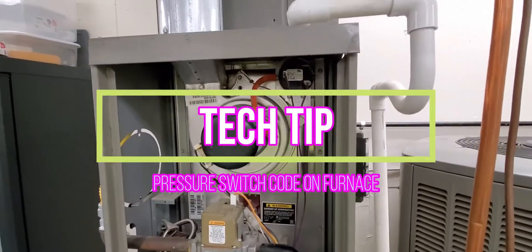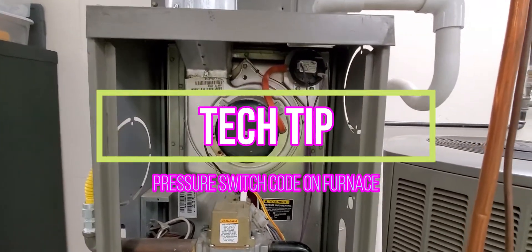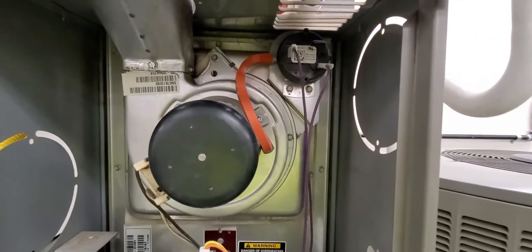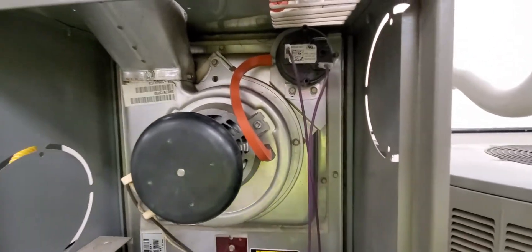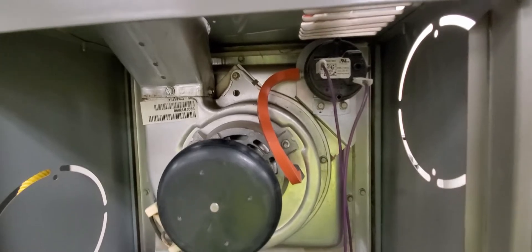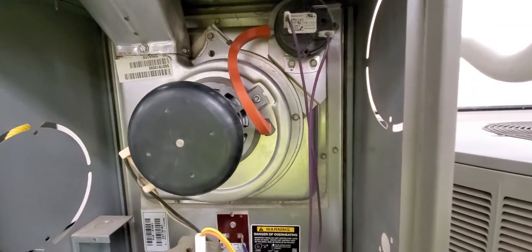A lot of times if you get a pressure switch error on your circuit board, I would check the hoses first and make sure that the ports aren't blocked. That's a pretty common problem in some of these. Take the hose off and then blow through it.